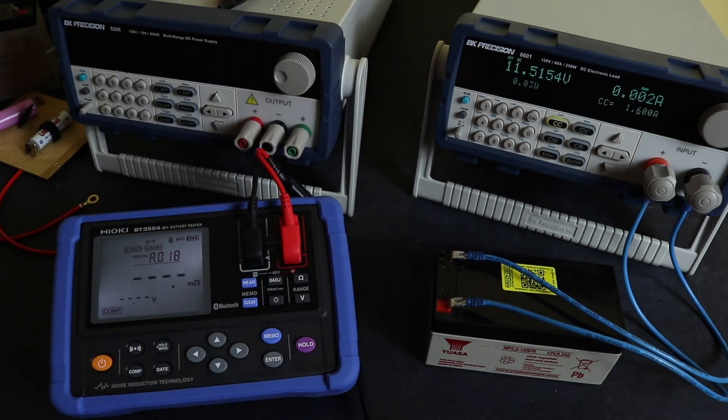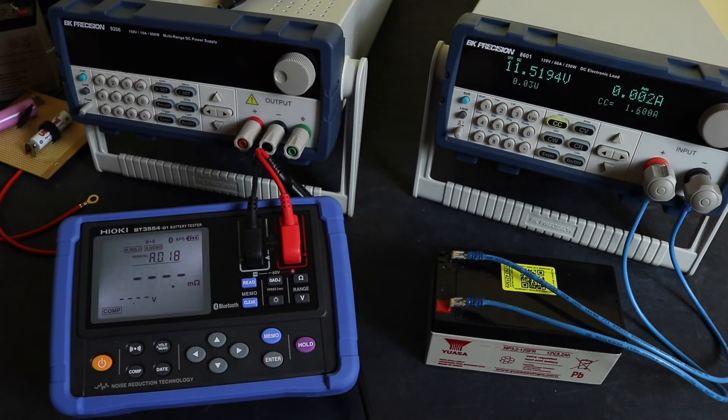On the resistance, but normally this is supposed to be 50 milliohms. If you'd have taken the reading with it in a discharge state, you'd have thought that this would tell you that the battery was faulty when in fact all it is is discharged. So let's say you'd only ever use these instruments when the battery's on float charge and take the readings then.